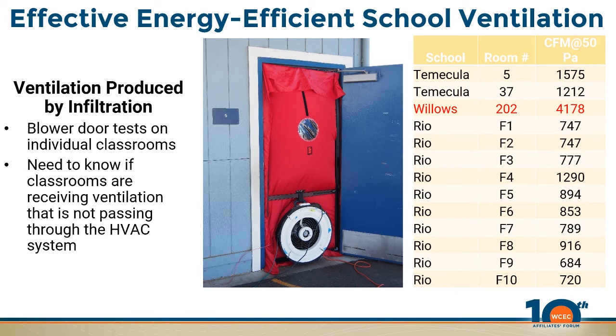Roughly speaking, this is a measure of the leakage of the building. They're all pretty good, except for Willows here, which is about a factor of 4 higher than the others, which is an older school. In that case, I think there's a decent probability—we haven't done all the modeling to see how big it will be, but a decent probability—that there's ventilation coming from something other than the building's ventilation system. Basically, the wind blows in on one side and out the other, and at that kind of leakage it's very hard to maintain pressurization of the space.